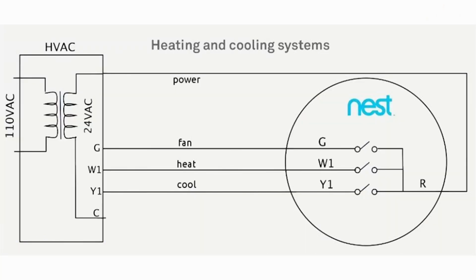The red wire carries 24-volt power from the HVAC control board to the thermostat. The thermostat controls heating, cooling, and fan operation by connecting the red wire to one of the relay wires to complete the circuit. When the red wire connects to the yellow wire, the cooling AC turns on. When the red wire connects to the white wire, the heating furnace turns on. When the red wire connects to the green wire, the fan blower turns on.